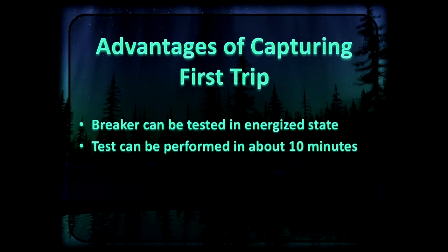Secondly, this test can be performed in about 10 minutes. It's a real quick test, and it gives you a quick and dirty look at the breaker, and it helps you determine if you need to do other tests to determine its condition. And third, this device allows you to overlay different operations so that you can analyze the speed that it's opening today compared to it opening 2 years ago.